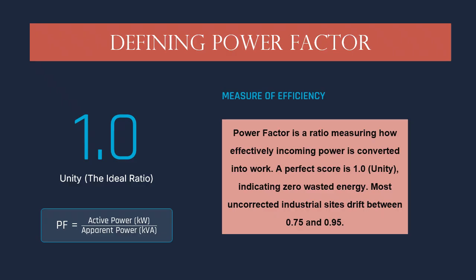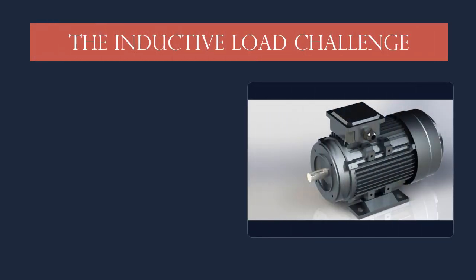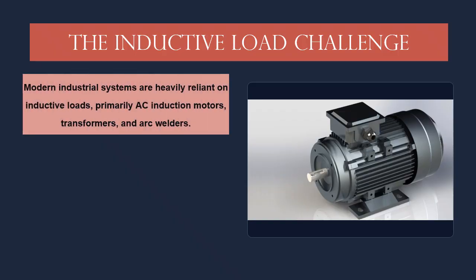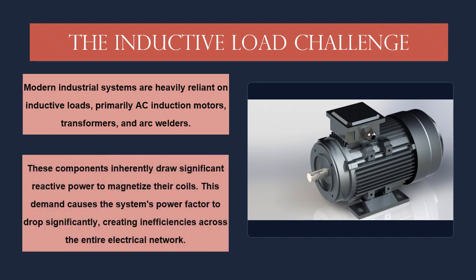The inductive load challenge. So, what drags this number down? The challenge lies in our heavy reliance on inductive loads. Modern industry runs on AC induction motors, transformers, and welders. These devices act like sponges for reactive power, drawing massive current just to magnetize their coils. This inherent demand causes a lag in the system, dropping efficiency across your entire network.